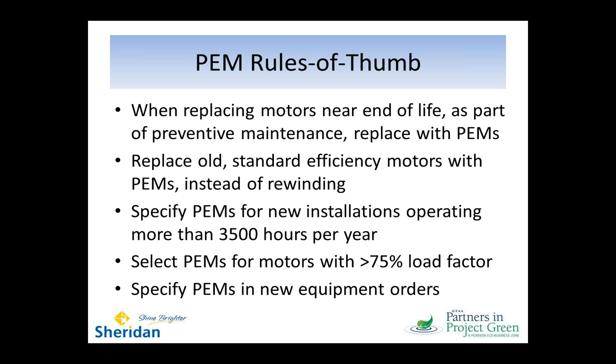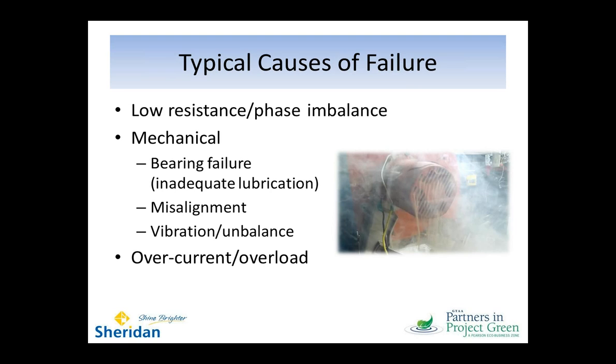And if you've got motors that are operating more than 75% of the time, then also look for premium efficiency motors in those applications, because the economics are going to work in your favor. We want to talk also about preventive and predictive maintenance. There are a lot of causes of failure in these. Some are related to phase imbalance, so a disparity in voltages between the phases feeding a motor causes all kinds of currents in the rotor and the stator that heat them up, and that heat causes vibration. It causes premature wear of the motor, not good for it at all.